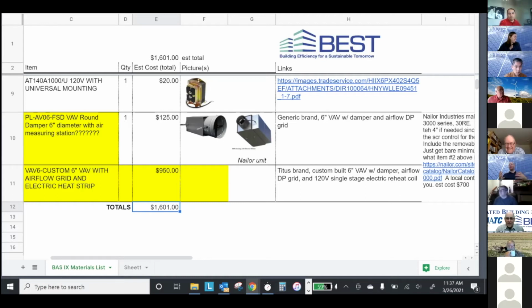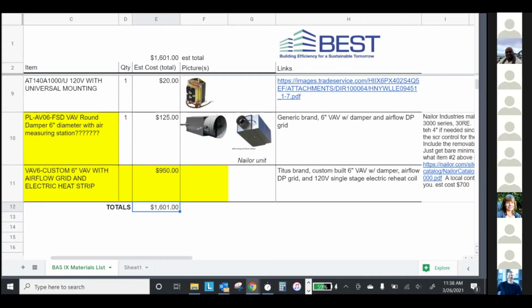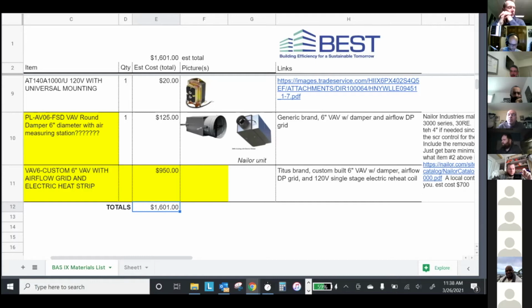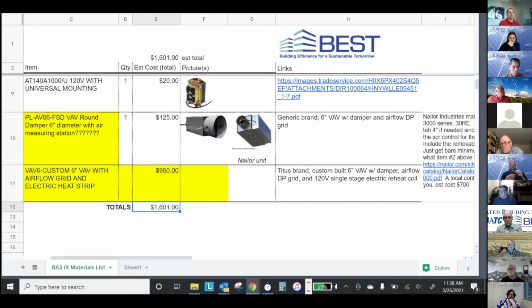So we are focusing on EasyIO and Contemporary controls. And I know some of you familiar with Contemporary controls are raising your hand, saying wait a minute, Contemporary Controls doesn't have a Sedona-based VAV controller yet, so how can we do that? The truth is the major component you need on one of these VAV controllers is an airflow monitoring station, but all that is, is a differential pressure sensor. So if you have a 0 to 5 inch differential pressure sensor in your lab, you can wire it up to any of the EasyIO controllers, whether it's an FW, FG, FS, or a 30P, or if you've got one of the Contemporary controllers, same thing. You can use that differential pressure sensor and make it work for this project. That may be another way to reduce costs if your budget is a little tight right now.